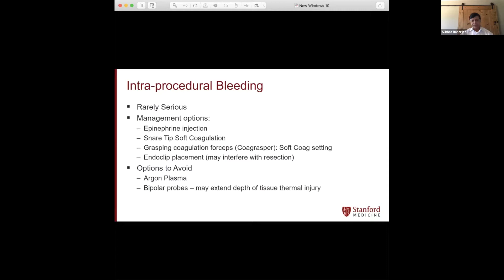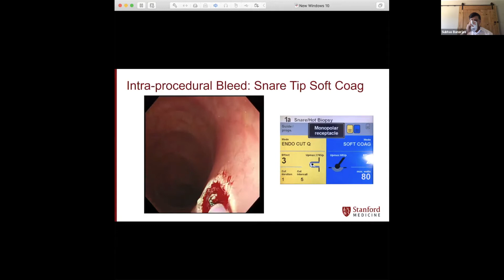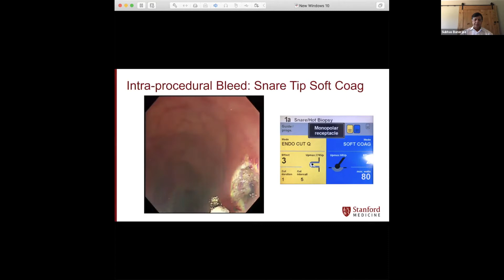So here's a video of snare tip soft coagulation. You want to set your electrosurgical unit at the soft coag mode in your blue pedal, typically effect 4. You stick out the tip of your snare, very lightly touch tissue, and stomp on your pedal. And this stops bleeding from small vessels quite effectively.